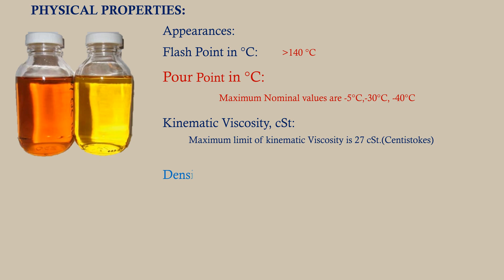Density in grams per cubic centimeter: higher density of transformer oil means higher viscosity, which in turn affects heat dissipation. The normal range of density should be 0.85 to 0.89 g per cubic centimeter.